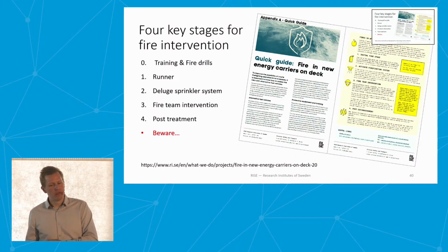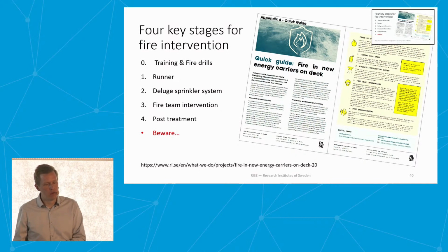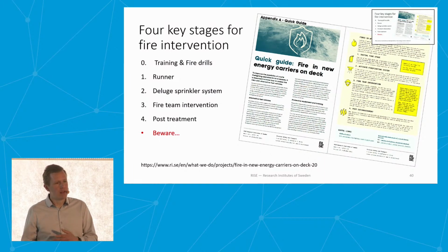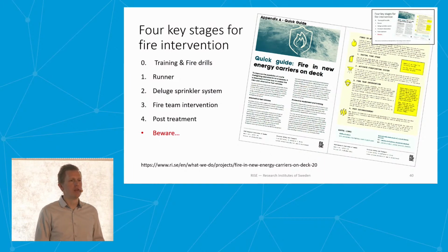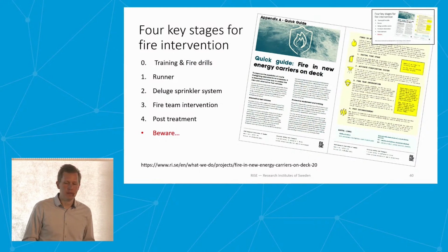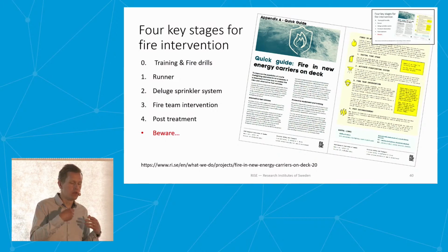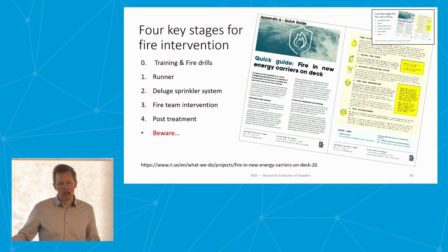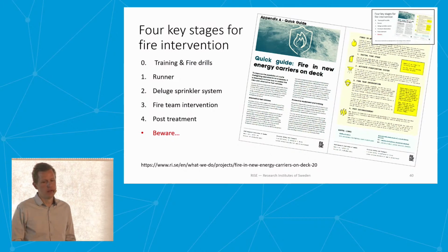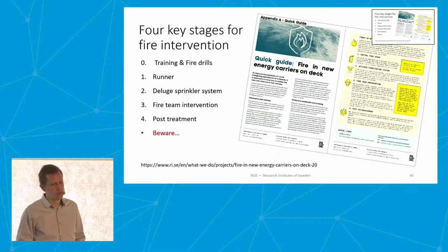If you can extinguish the fire early, that's beneficial, since you don't have to deal with a fire-exposed or damaged battery that could reignite. Also for gas tanks, as the tests showed, if you try to cool the tanks, you could have some time to fight the fire - it's only after about 20 minutes or so that you should activate the drencher as well.